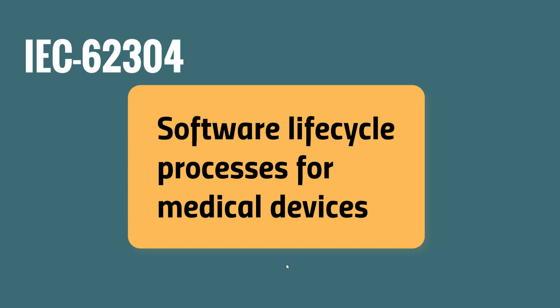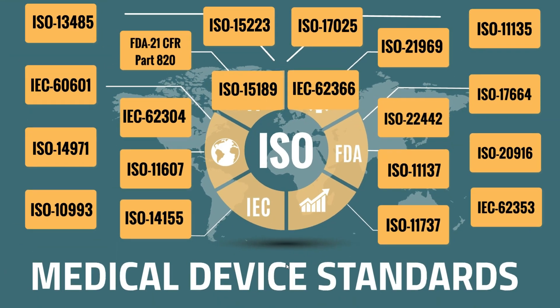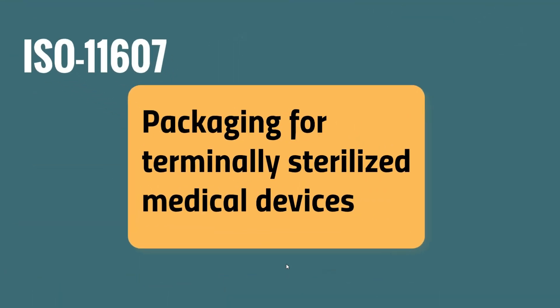7. ISO 11607 — ISO 11607 is the principal guidance document for validating terminally sterilized medical device packaging systems. Packaging must comply with ISO 11607 in order to satisfy European regulations and obtain a CE mark. ISO 11607 is also an FDA-recognized consensus standard.